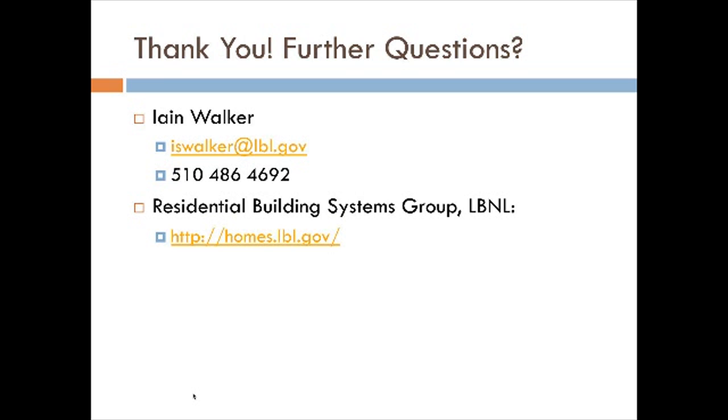Okay, great. The next question, in climate zone 3, mixed humid, what would you recommend for dehumidifying the whole house makeup air, short of having to add an ERV? Yeah, I think that if your concern is about humidity control, an ERV can help in the sense that if you've put in a dehumidifier and actively are dehumidifying a home much below the outdoor humidity, the ERV will certainly mean that that dehumidifier has to run less. But the ERV on its own is not going to be enough to control humidity in your home.